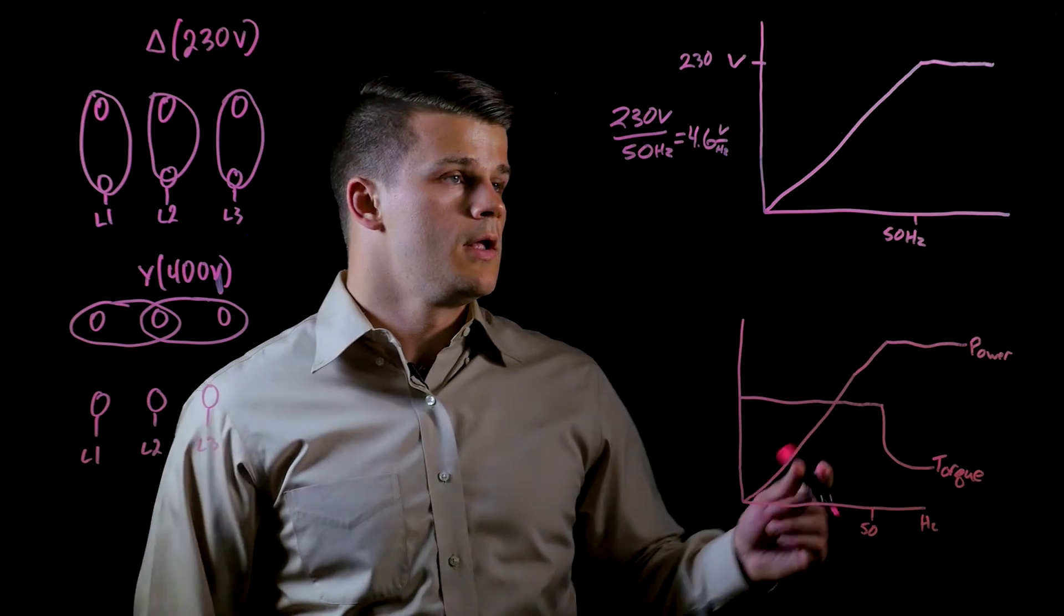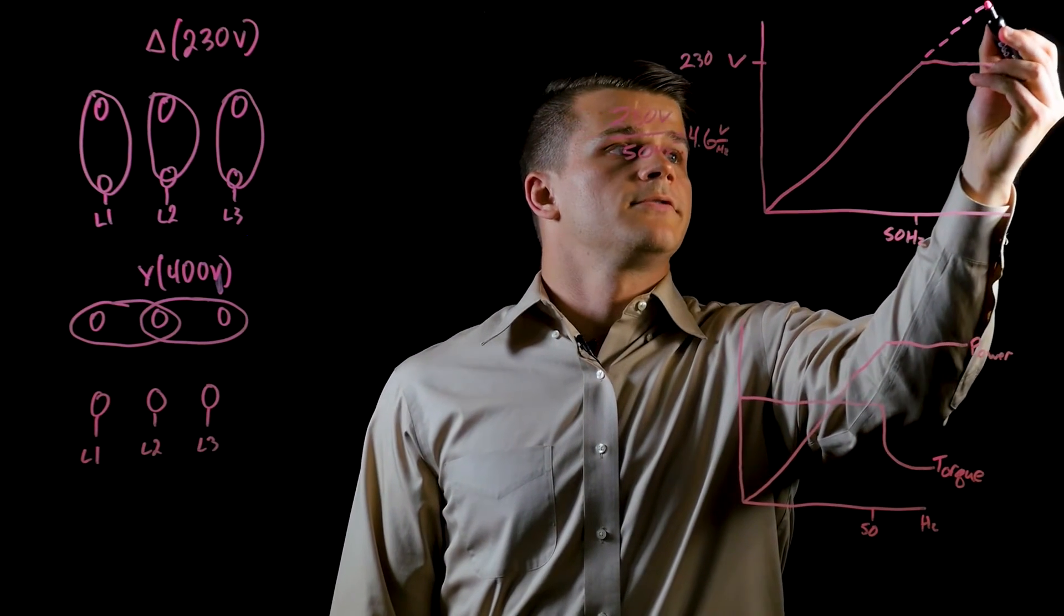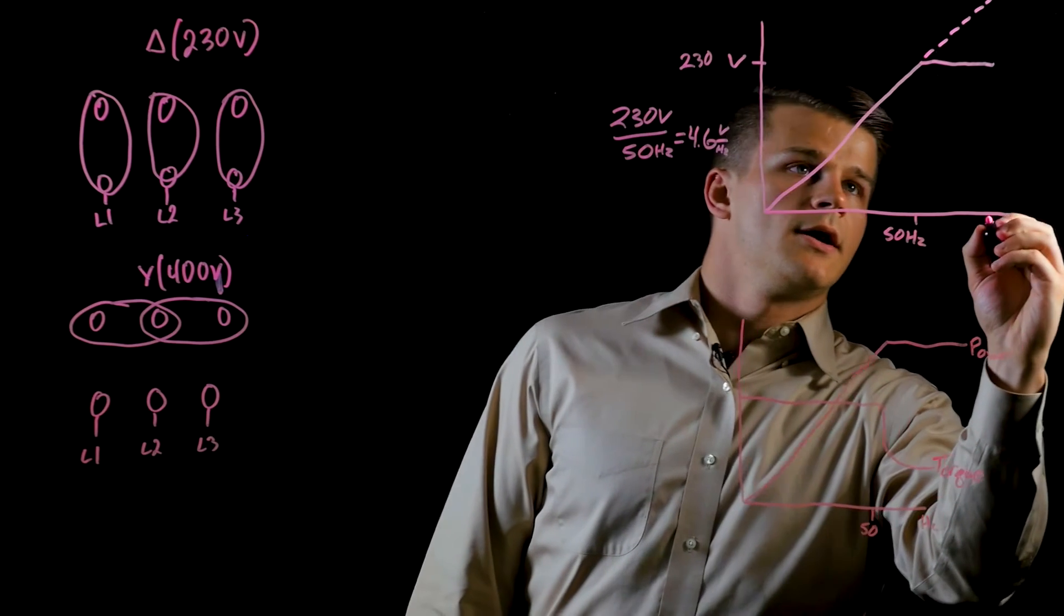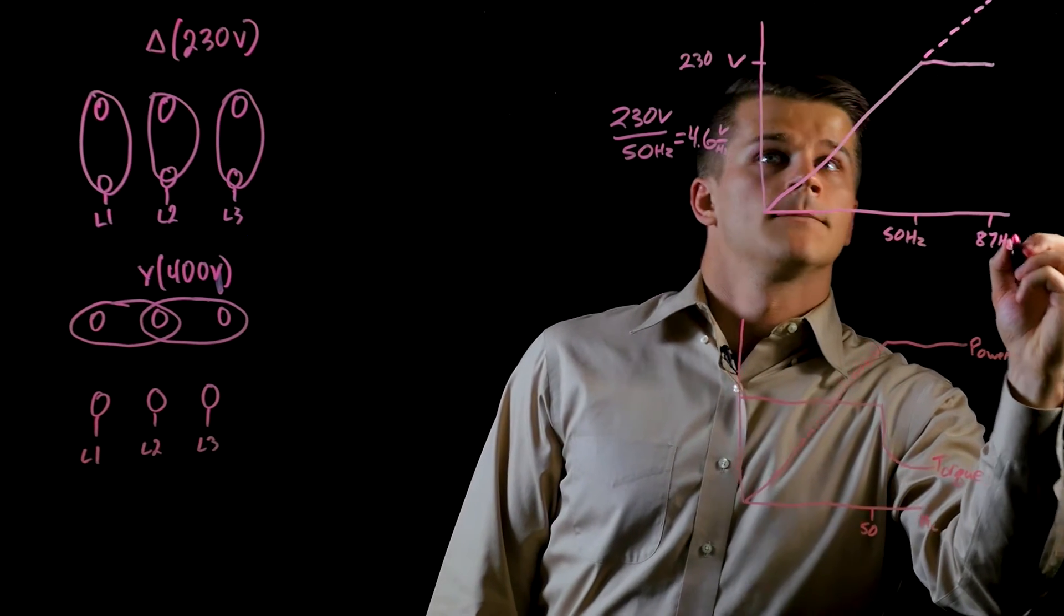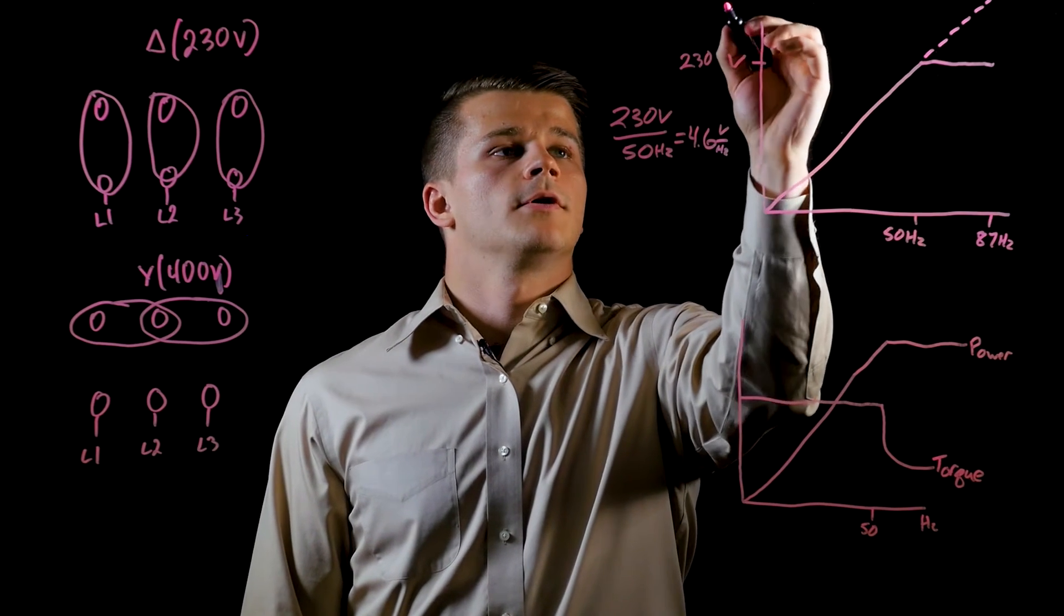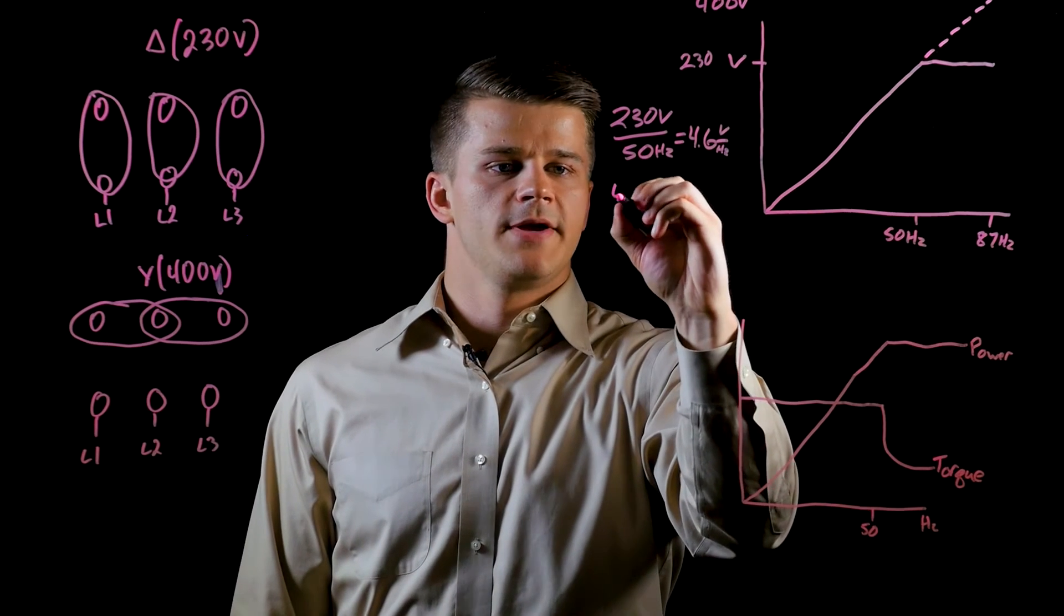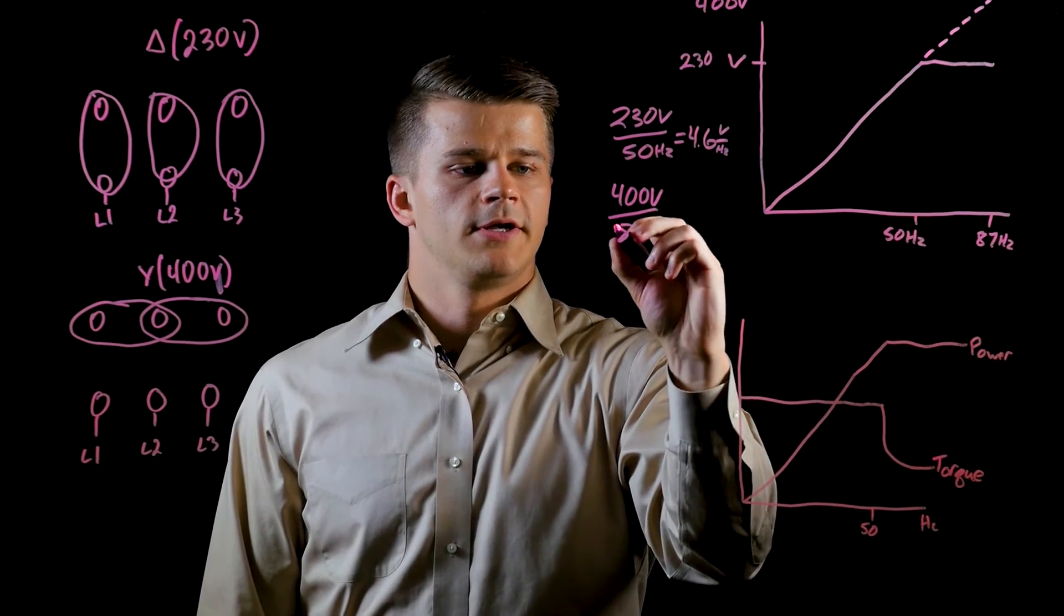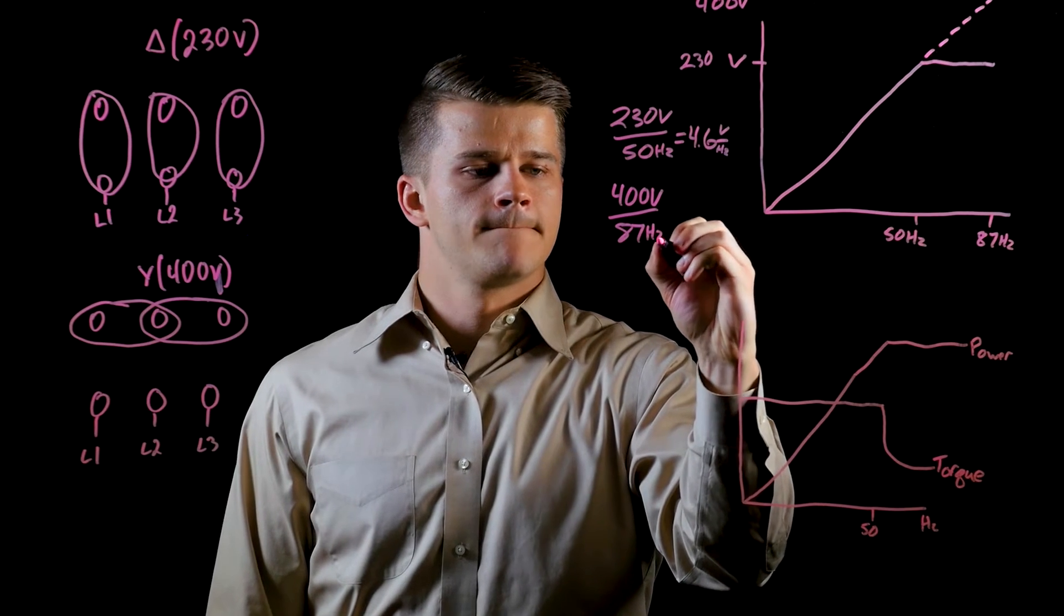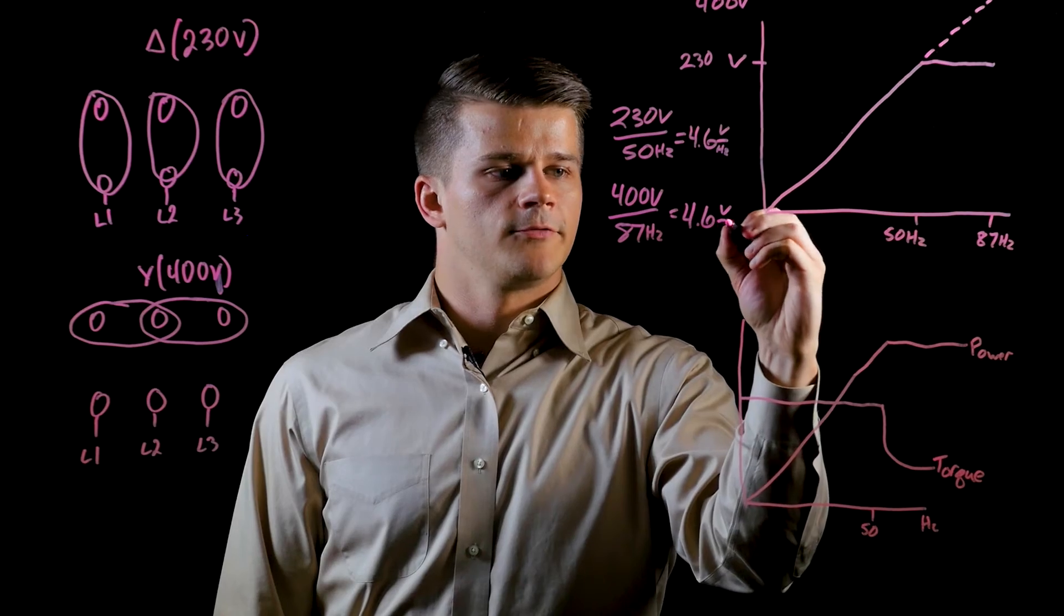If we imagine increasing this straight out to 87 Hertz, we go up to 400 volts. If we do the math again quickly, we have 400 volts over 87 Hertz, and that is the same 4.6 volts per Hertz.